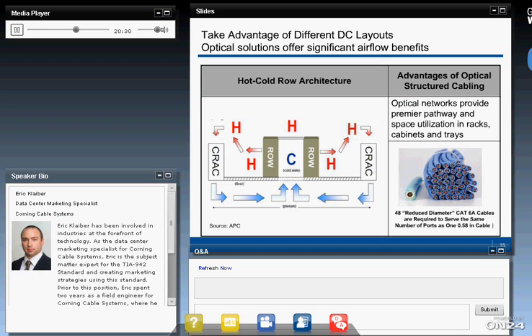If you look at the right picture, it shows 48 Cat 6A cables, quote-unquote reduced diameter cables, required to serve the same number of ports as can be served by a cable that's only 0.58 inches in diameter. So you can see the amount of air blockage when I need to put that much copper cabling in, not including the weight that copper cabling has. The air blockage alone is able to stop this hot aisle, cold aisle from working efficiently.